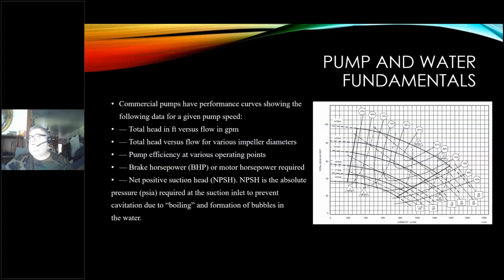Pump efficiency at various operating points. This is going to be critical as we talk about selection and how we're operating. The efficiency is where a lot of questions get answered. Brake horsepower, that's our part in energy management, what we actually have to have in order to move the water, and if we can make any reductions or if it's practical. The net positive suction head, that's what I was talking about at a cooling tower. They did not have enough pressure pushing the water into the pump to get the water moving through the pump at the right flow rate.